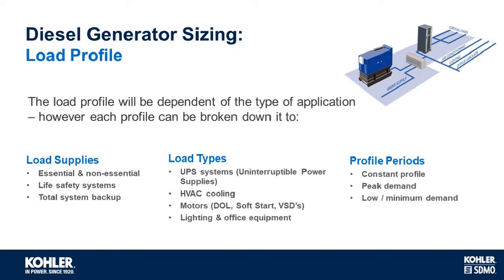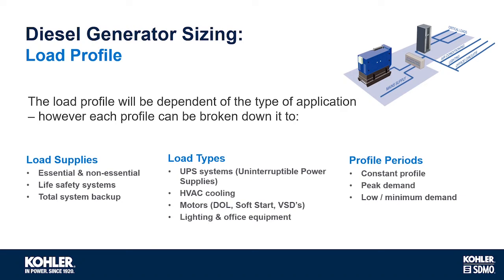Lastly, the profile periods. Is the load constant? Is there a peak demand? Is there a low or minimum demand? It's an important consideration. Generators are not designed to run for long periods with low load, as this can actually affect the ability of the engine to provide its full power when it's required and can impact on service intervals.